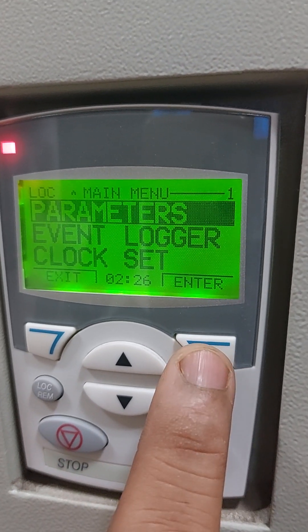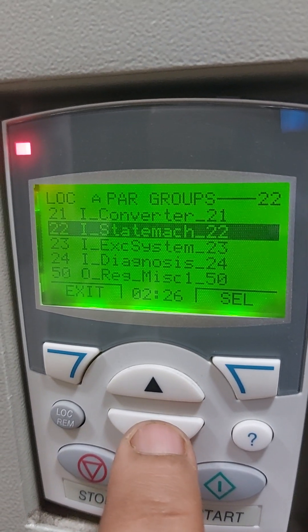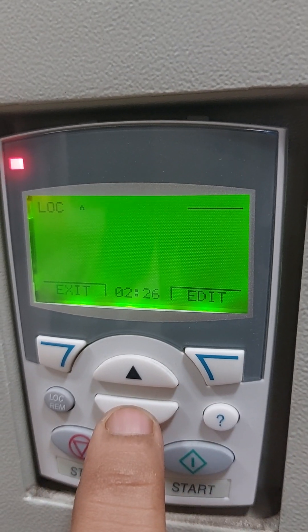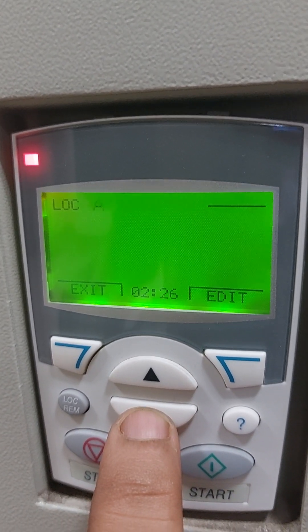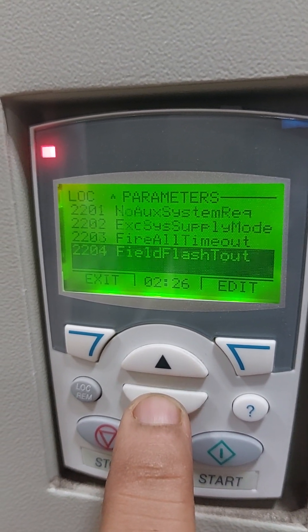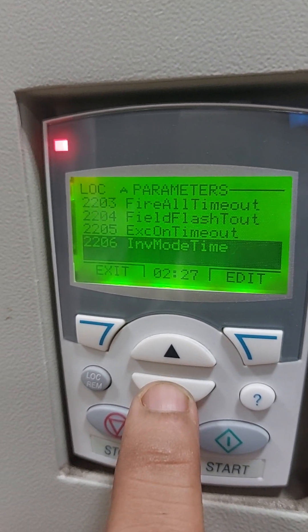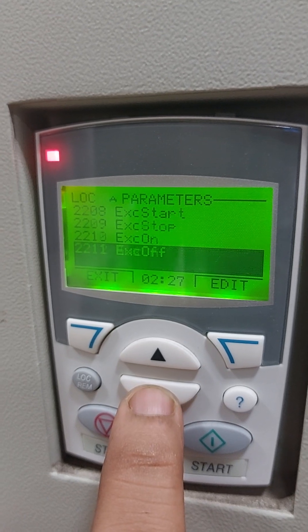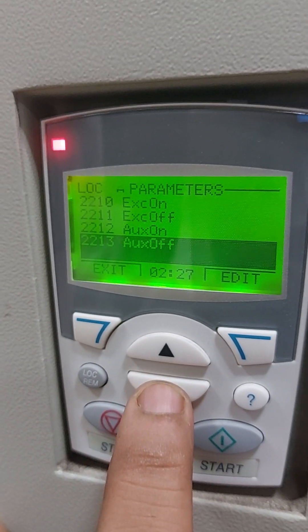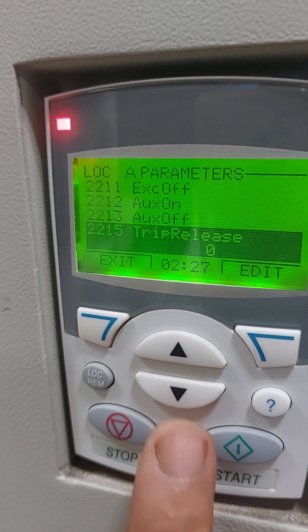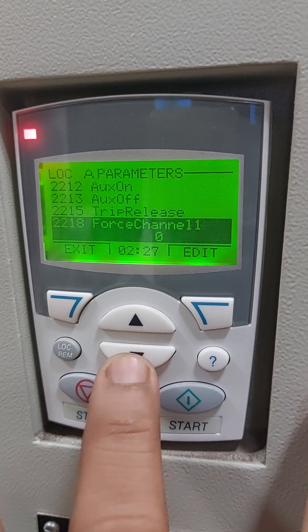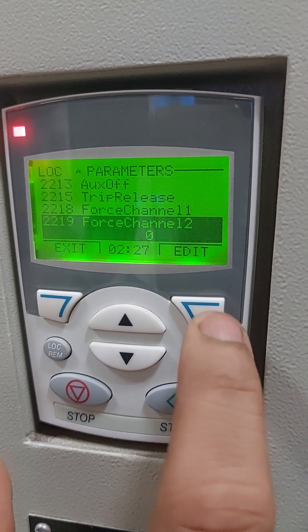Now go to menu, go to parameters. The codes are 2218 and 2219. Select and come down here. Parameter 2218 is for channel 1 and 2219 is for channel 2. Presently the AVR is in channel 1 and I want to change it to channel 2, so I will use parameter 2219. This is channel 2, and I am going to force it.